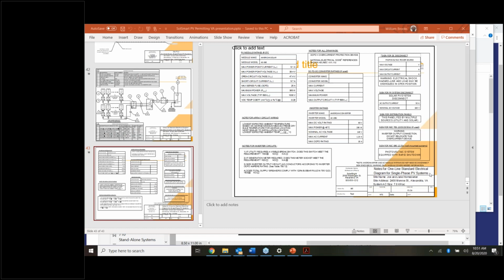So the question may have been related to the fact that the way the code was written in previous code cycles before the 2017 code, there was an article, in Article 690.47(D), it suggested that an additional array electrode might be required. The intent of that section was to say that if the building or structure you were installing on did not have an electrode system, let's say it's a detached barn that had no electricity in it, so it had no grounding electrode system, you would install a grounding electrode system like 2 ground rods on that barn, and then you tie the equipment grounding conductor from any disconnect equipment or distribution equipment to that grounding electrode system, and it has the benefit of local grounding as well as some lightning benefits and stuff like that.